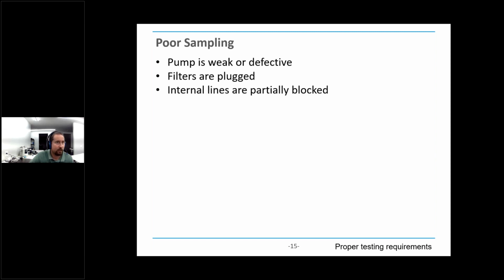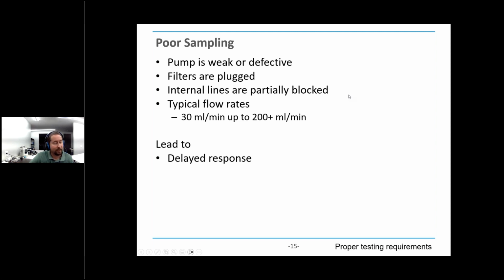The flows that we're talking about are actually really small for gas monitors. They're 30 milliliters a minute up to 200 milliliters a minute. This is much less than, say, a ventilator, which is measured in liters per minute. And if you have poor sampling, you can get a delayed response in the waveform and the numbers. So a patient may be having an issue and it might be delayed 30 seconds, a minute longer than it should be because of poor sampling, and that's critical time.